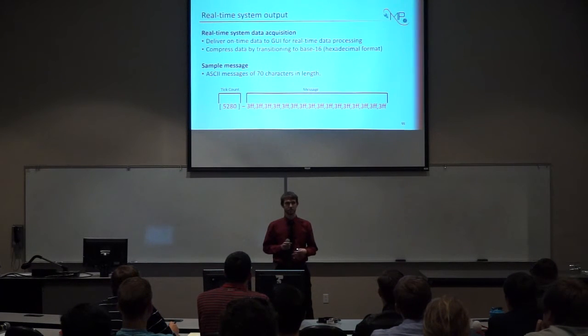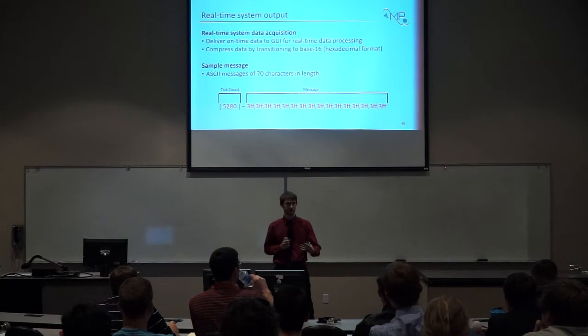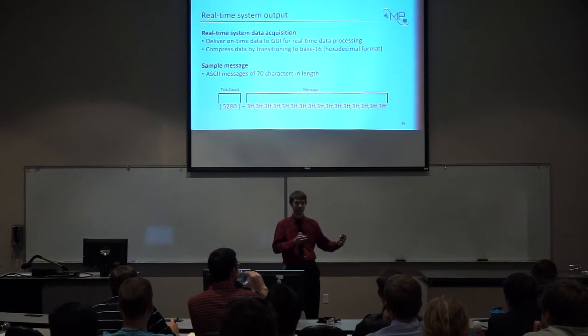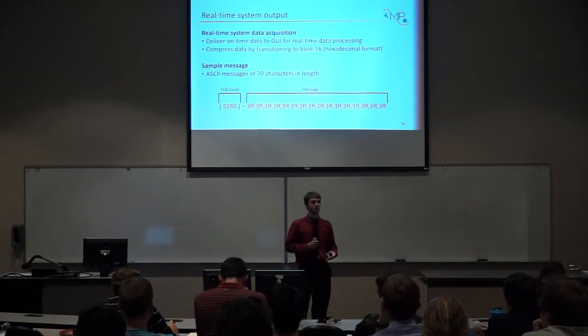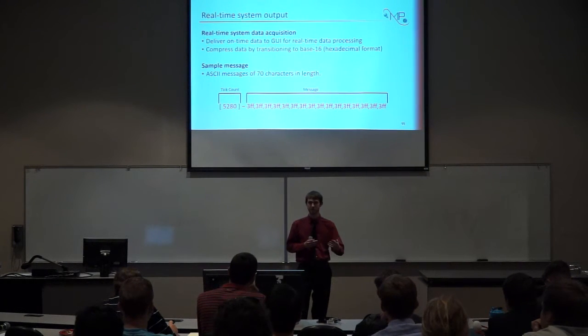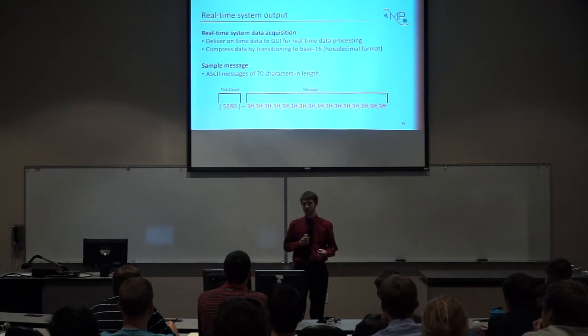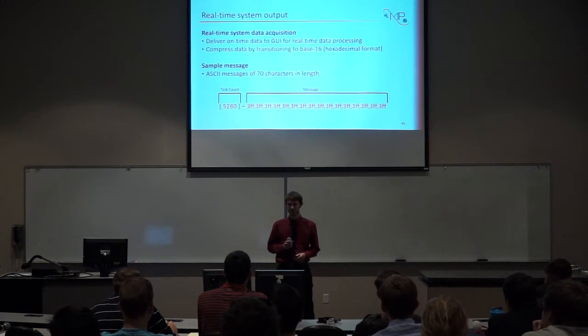The tick count is roughly the elapsed time in milliseconds since the test started, and gives you an overview of when certain things have happened, whereas the message buffer will most commonly be either an error message or something that the operator needs to look at. But it's most commonly the analog to digital converter values of all 16 channels in succession.